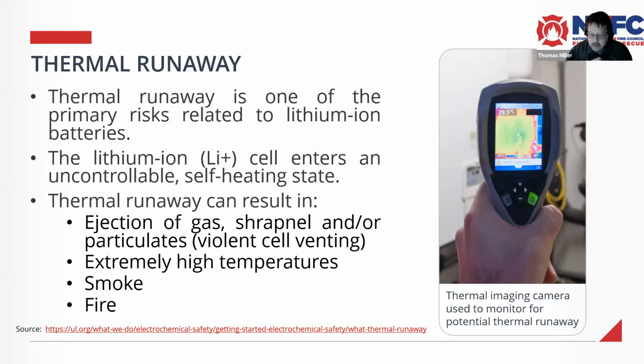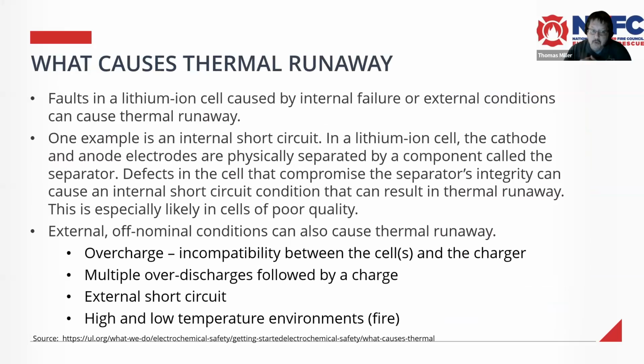Just bad. So what causes thermal runaway? It's an internal short in the battery, something breaking down in the mechanical process. The cathode or anode electrodes get physically separated through damage from a crash. There can be all kinds of different things: defects in the cell, moisture inside the battery, overcharging or undercharging of the battery, multiple over-discharges where they took the battery below 20%, an external short circuit where they wired it up wrong, and high and low temperature environments, including fire or extreme cold, 30 degrees below zero, probably might have a problem.